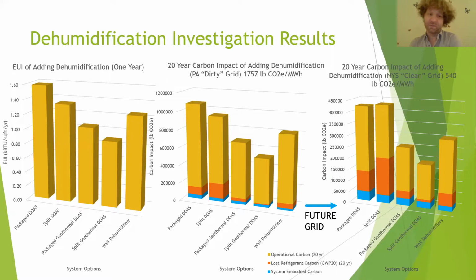So they rely on electric heat a little bit more. Packaged geothermal does really good, split is even better, and the wall dehumidifiers come in the middle. That's because they're only treating the room—they're watching the humidity in the room, so they're just not dehumidifying quite as much. It's more about controls than actual efficiency of the units. So even though they're a little less efficient, being just a little tiny thing sitting in everybody's apartment, they get the benefit of not dehumidifying when they don't have to, whereas a packaged system on the roof definitely does—it can't always hit exactly the right spot.